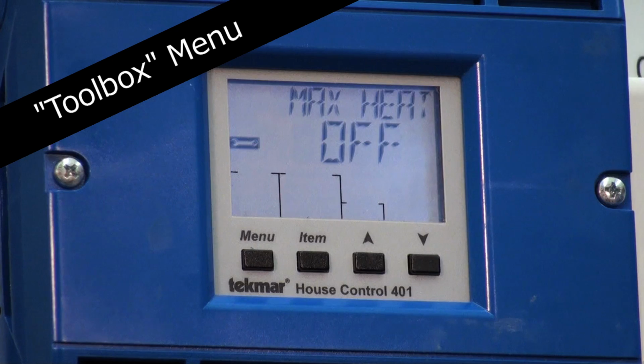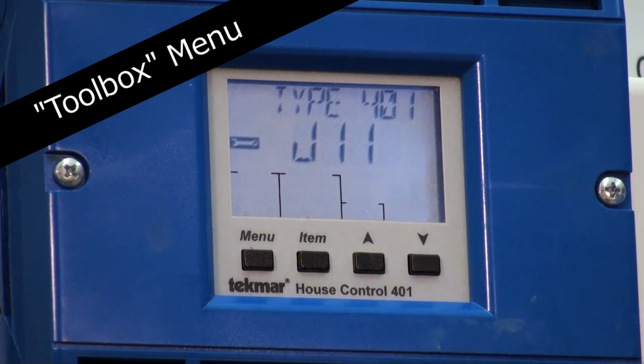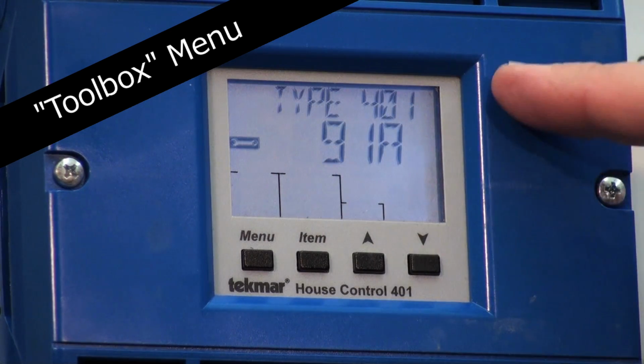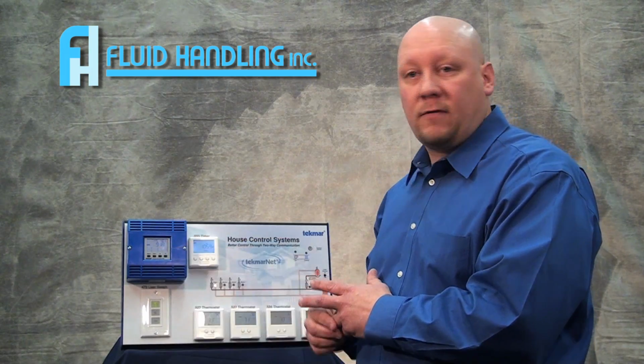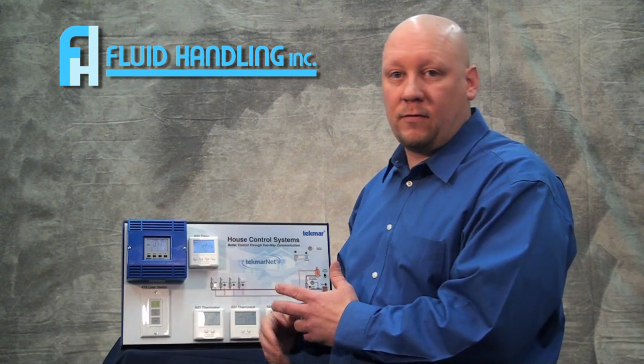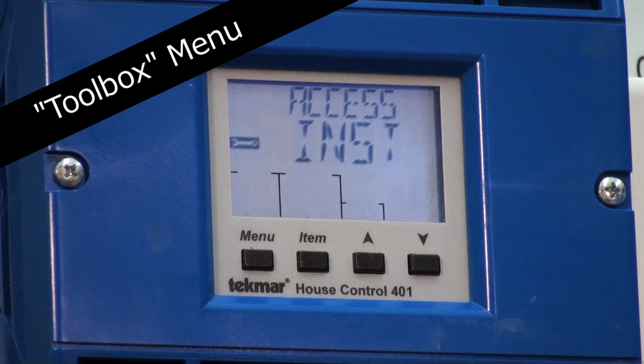You can also max heat. Here's where, if you know you want it running for 2 hours to get everything set up, you can set the max heat on here to 85 degrees and all thermostats. This unit will just run thinking it's trying to get to 85 degrees. And here we're showing it's a 401 and we're showing you the software version that's on the control. So if we were ever to have any issues, we could ask you the software version; here's where you would find it.